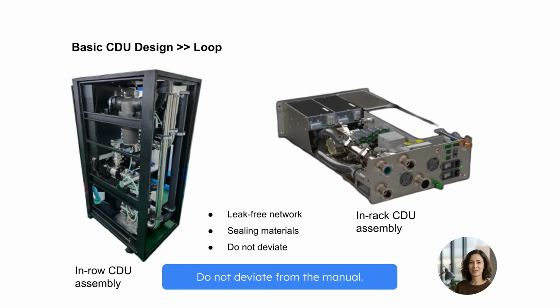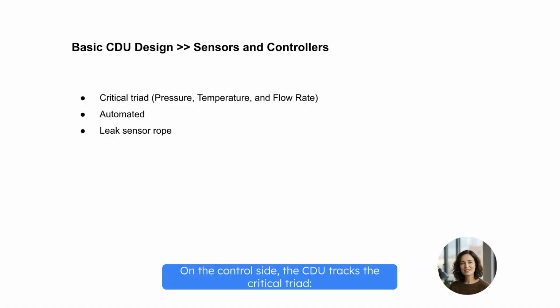Do not deviate from the manual. Strict adherence to assembly best practices is the only way to qualify the CDU. On the control side, the CDU tracks the critical triad: pressure, temperature, and flow rate. It doesn't just log data, it watches for deviations to trigger immediate operator alarms. Crucially, we rely on automated safety mechanisms. If a failure occurs, the controller must instantly cut pump power or isolate valves. And for physical protection, the leak sensor rope is the industry standard for containment.